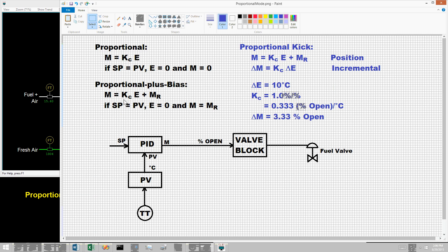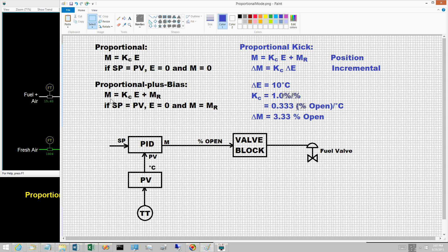The proportional mode equation, M equals K sub C times E plus M sub R, computes the controller output M. This is known as the position form. The incremental or velocity form is written in terms of changes or deltas.